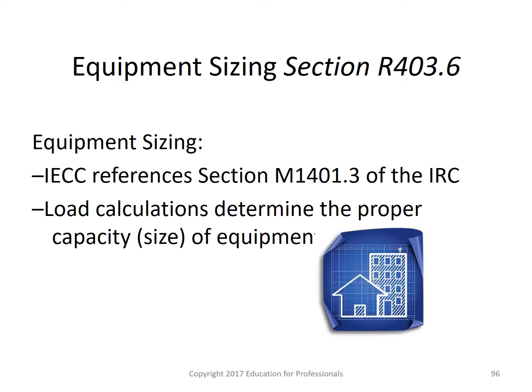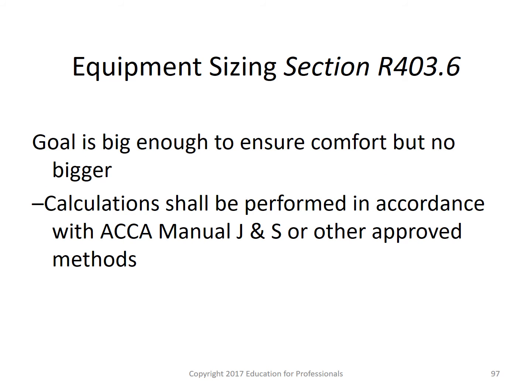Improper installation of components, in particular ductwork, has a negative impact on comfort, increases energy bills, and can dramatically degrade the quality of air in a building. Poorly designed and installed ducts can create conditions that may reduce comfort, degrade indoor air quality, and even threaten the well-being of the occupants. The goal is to have equipment big enough to ensure comfort, but no bigger than is needed.